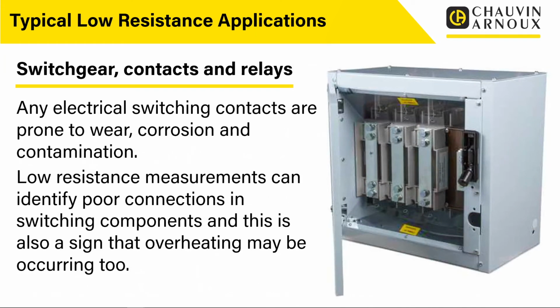Now, a similar application here is switchgear contacts and relays. Any electrical switching contacts are prone to wear, corrosion, and contamination. When we're talking about switching contacts, we mean the bits within the switch, the circuit breaker, the relay that touch together to make a good connection temporarily to carry that current. And if they pit or arcing burns them, or they get contaminated with soot or copper buildup, dust buildup, or anything like that, again, we can see that with a micro-ohmmeter. We can see that by doing a low resistance reading.